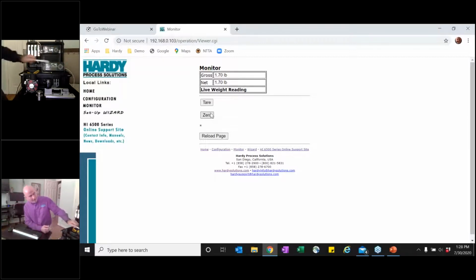All right, so now this scale is reading that we've got 1.7 on the scale. This one says we've got the correct 0.45. The monitor, because it's connected to this one, also gives us a 1.7. All right, now we need to do the span weight. So let's go down to the span weight. And now it says that the span weight's going to be 5.